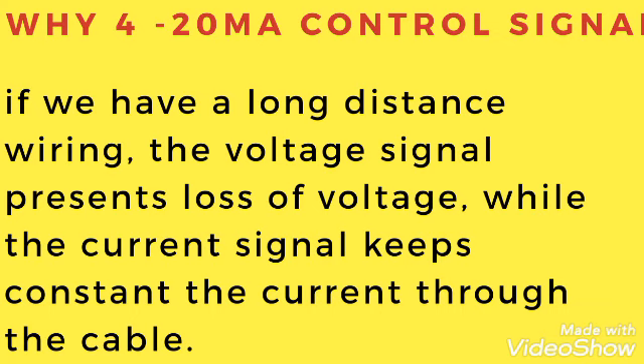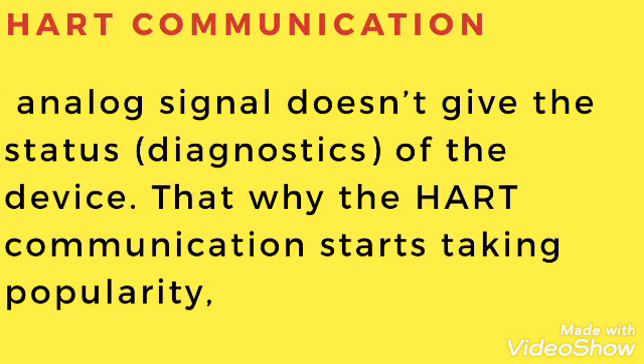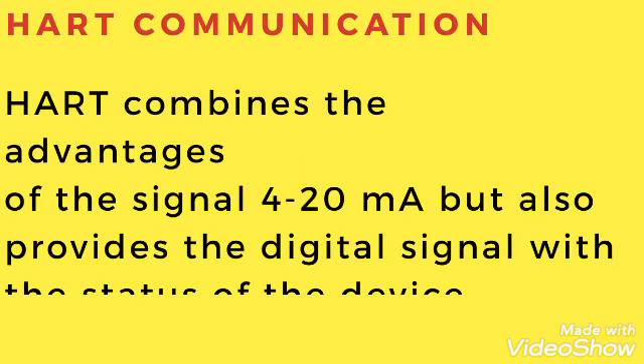If we have long-distance wiring, the voltage signal presents a loss of voltage while the current signal keeps constant. However, the analog signal does not give the status or diagnostic of the device. That is why the HART communication started gaining popularity, because it provides diagnostics.